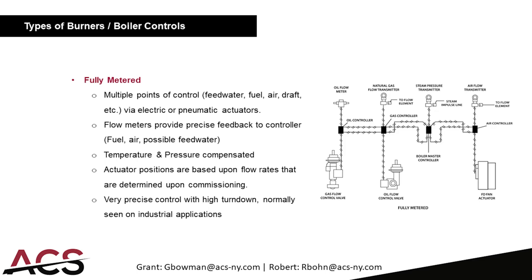The third control type uses flow meters with feedback. The controller sets a setpoint for oil — for example, 10 gallons per minute — monitors the fuel meter, and when it reaches that point holds it steadily at that flow rate. There is the ability to use temperature and pressure compensated meters. This is a very precise control and is normally used for industrial applications and larger water tube boilers.